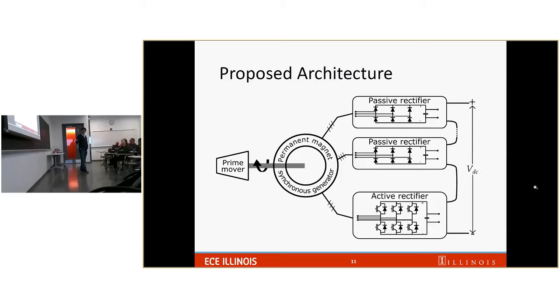So we need to attach an active rectifier in series with the passive rectifier. One property of the active rectifier is it can regulate its own DC bus voltage to virtually any value that we want. So in case the voltage drops on the passive rectifier, the active one can increase its own voltage to regulate the DC bus voltage at a constant value across the whole operating speed range. So that is the idea.